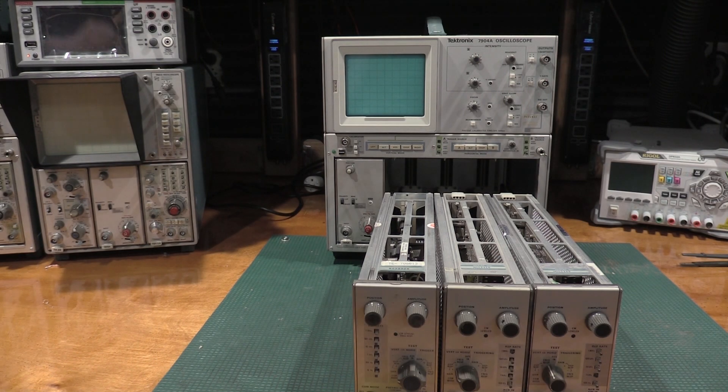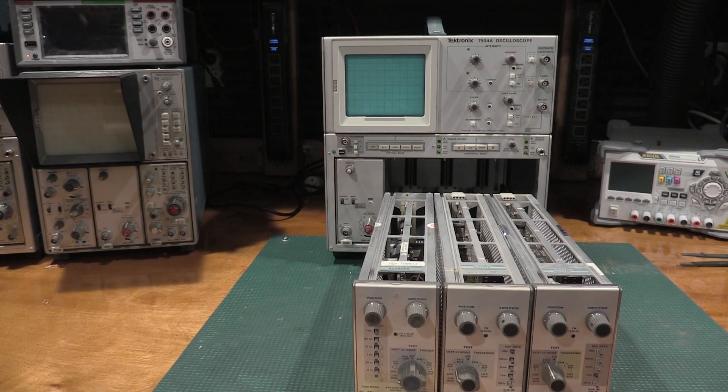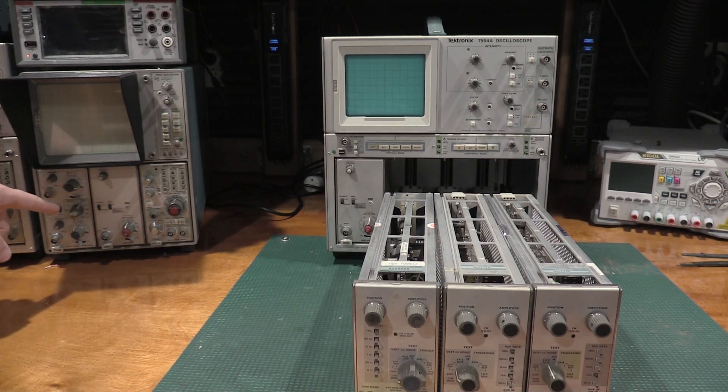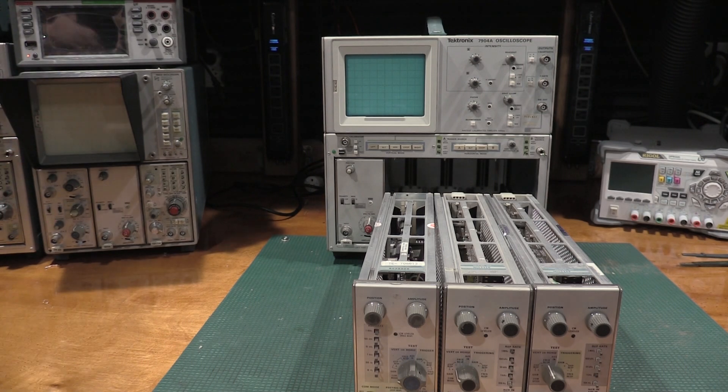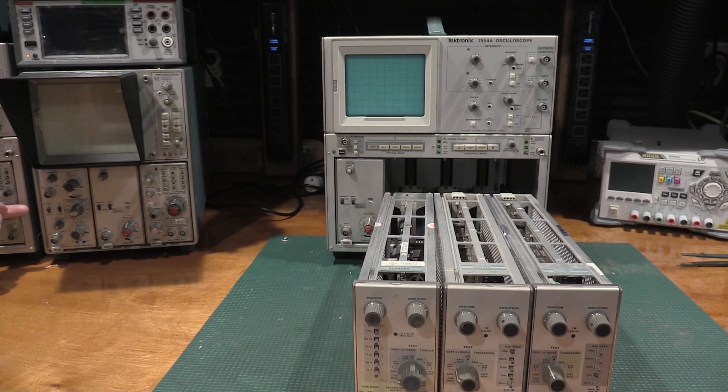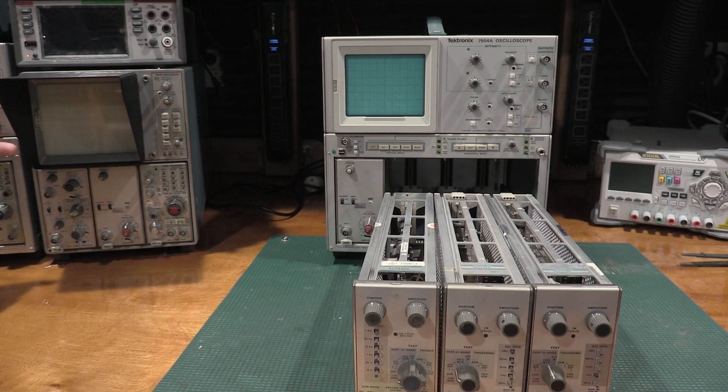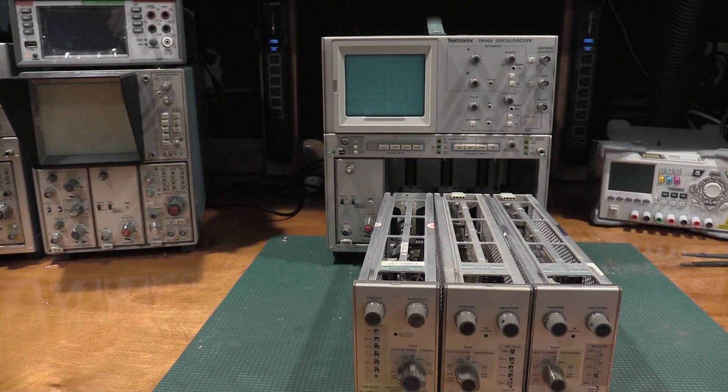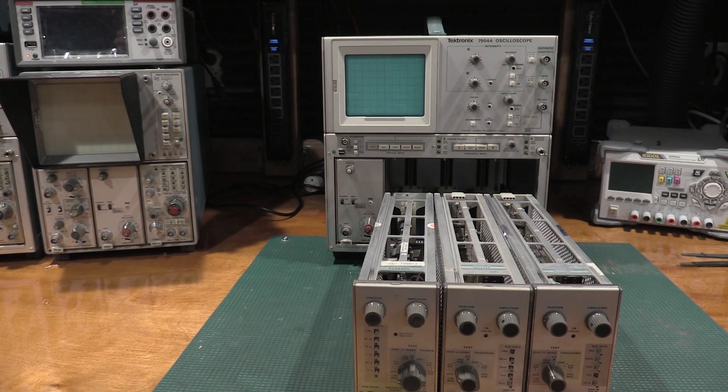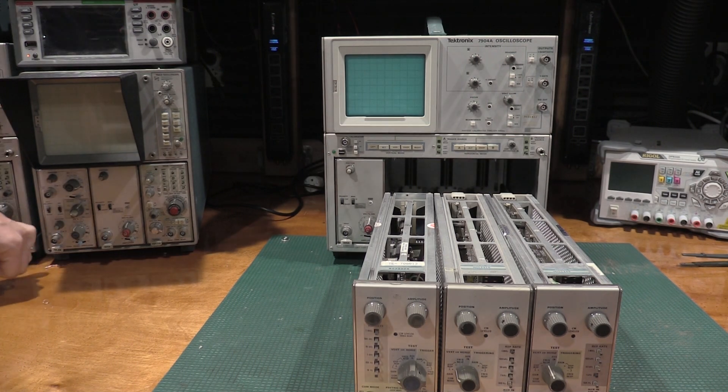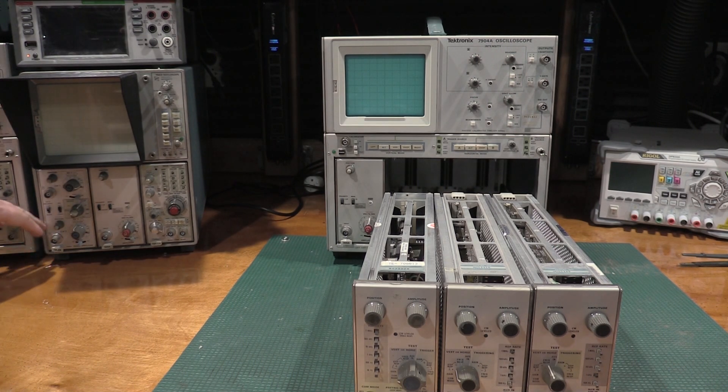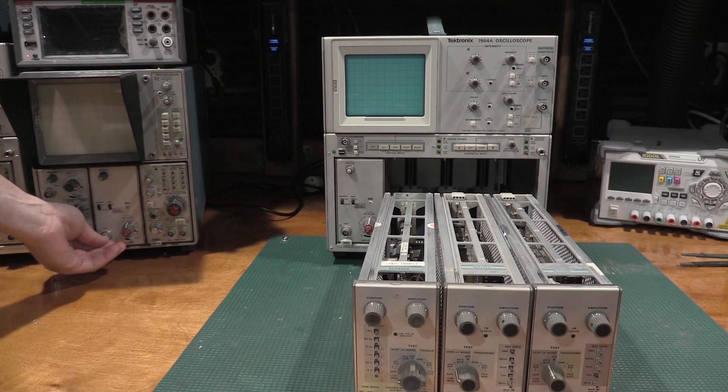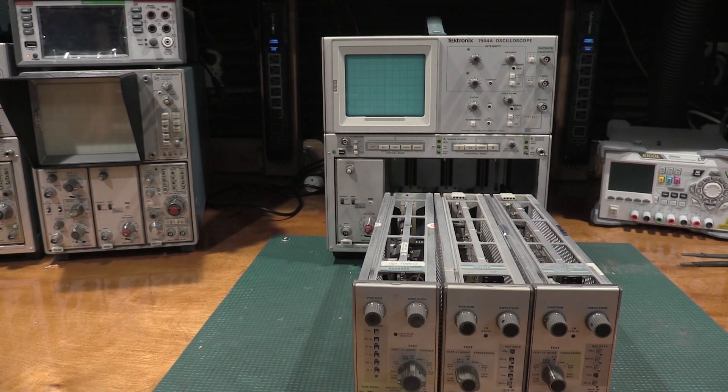The problem is, or the limitation, not really the problem, you lock the plug-ins to the base because in the signal path of the scope you have the signal path of the plug-in to the signal path of the frame to the output of the screen. As you're doing the compensations, especially the high frequency compensations, you're aligning the plug-in and the frame to each other. It'll meet spec, all the waveforms will look good, but the plug-ins will be locked into their frame. You can't pull this plug-in out and plug it in over here. You may have a completely different response curve.